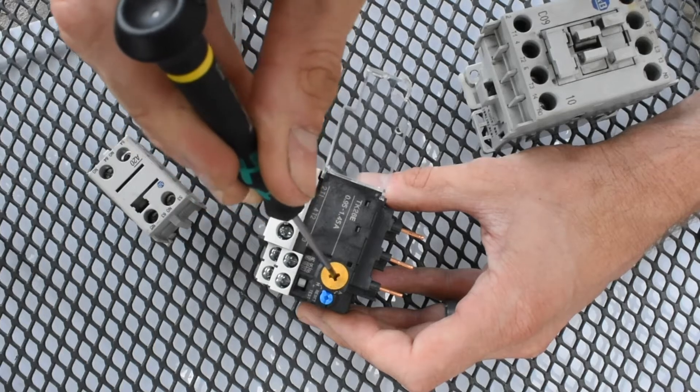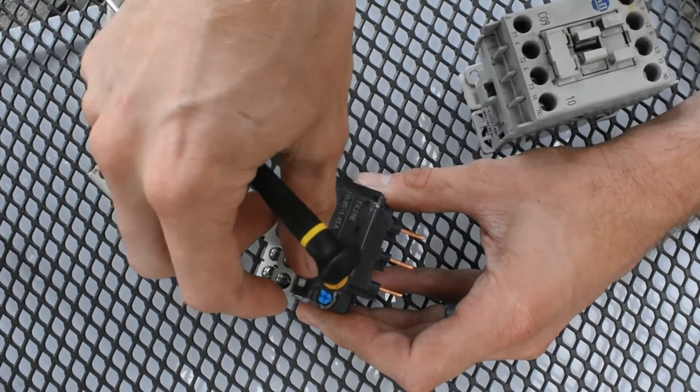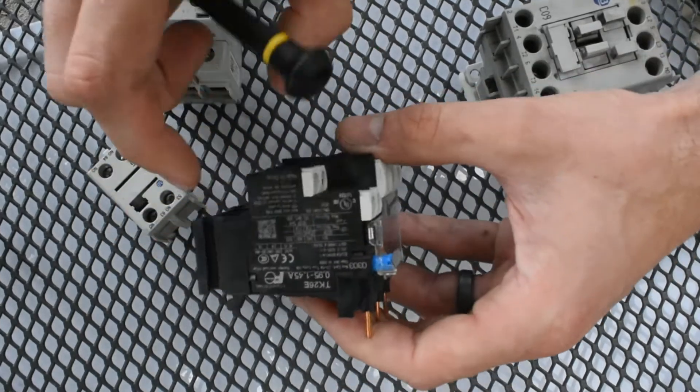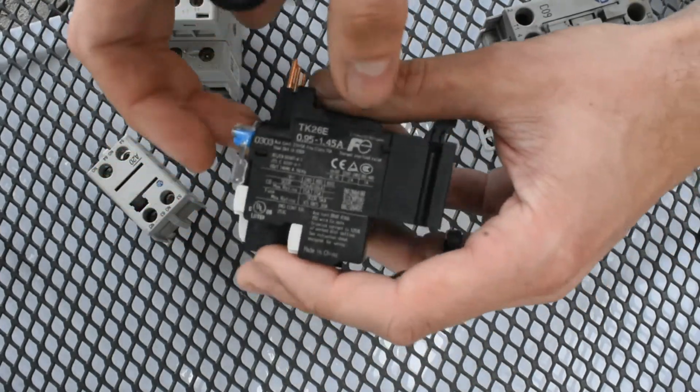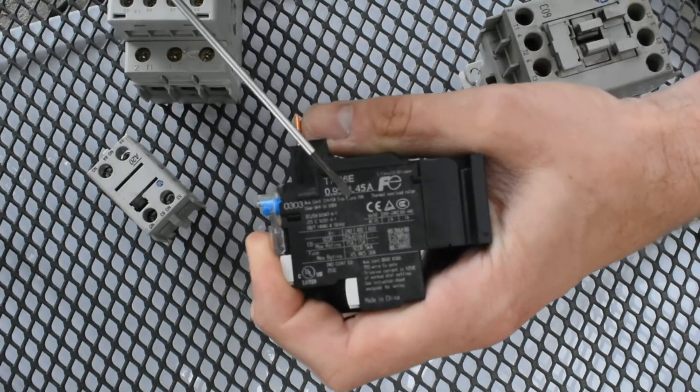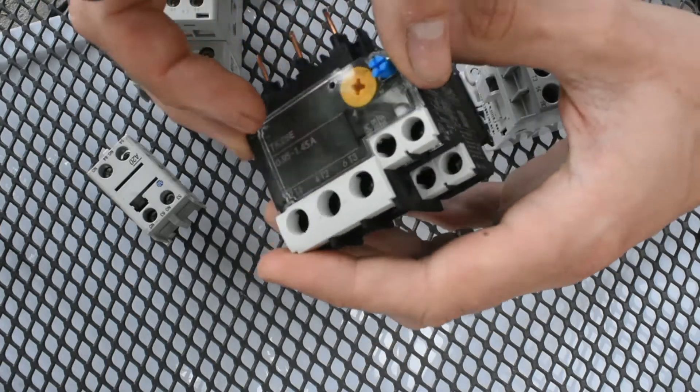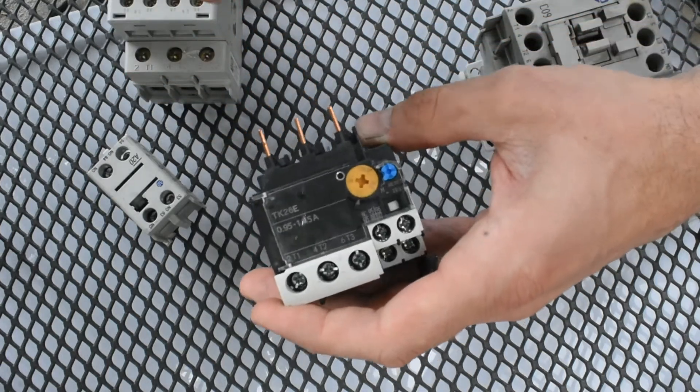You'll notice that this overload relay, as well, has a current adjustment. Now, this one has no selector switch for trip classes. So, if I look at the labeling on the side of it, let's see, here it says class 10. So, this is a trip class 10, which means 10 seconds of high current before it's going to trip.